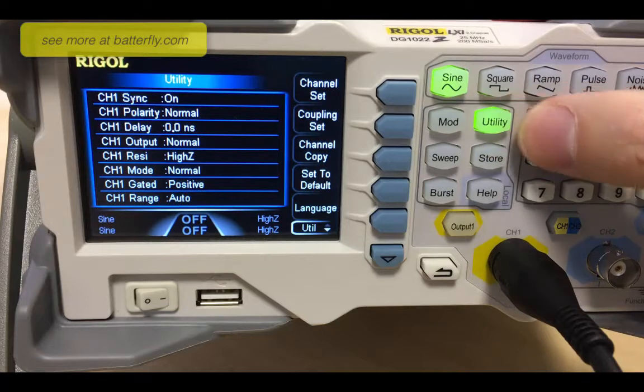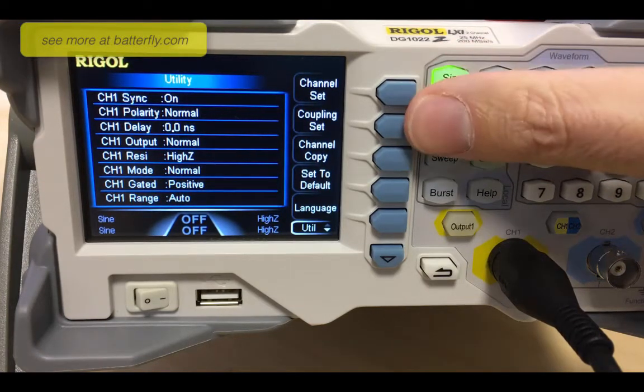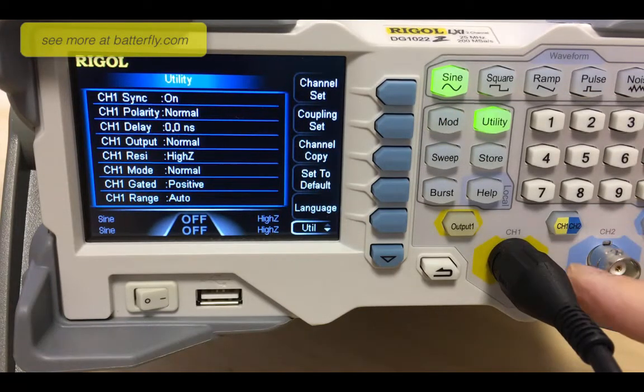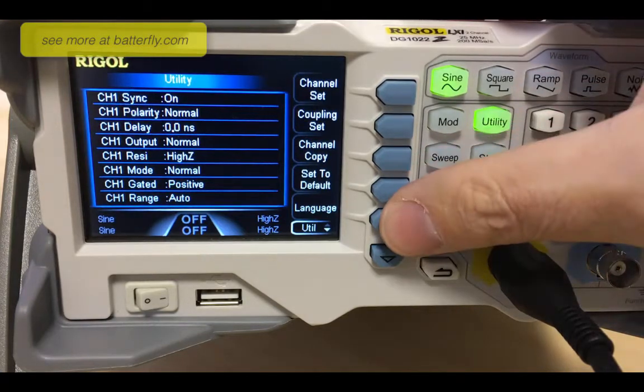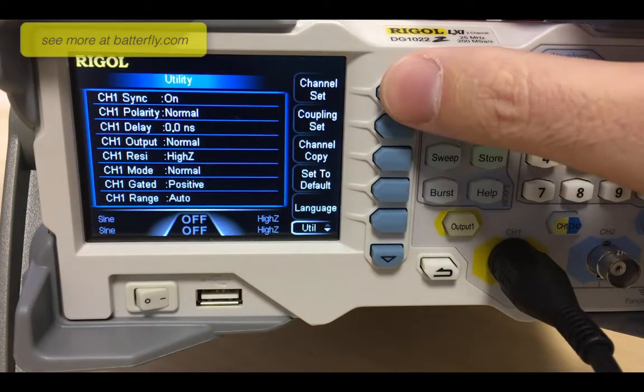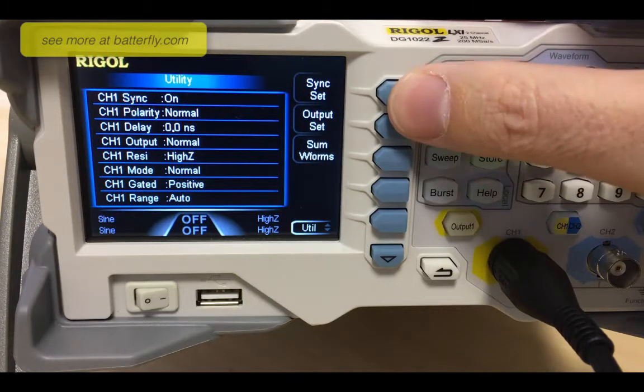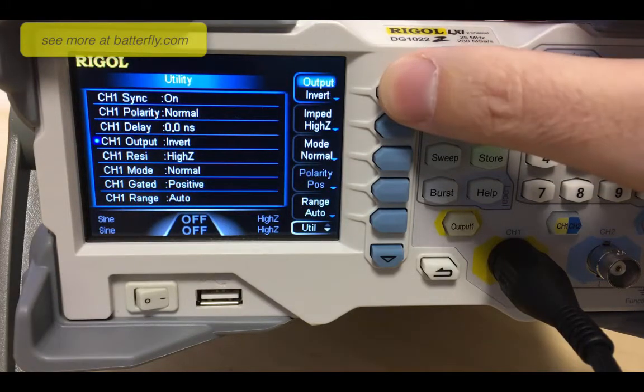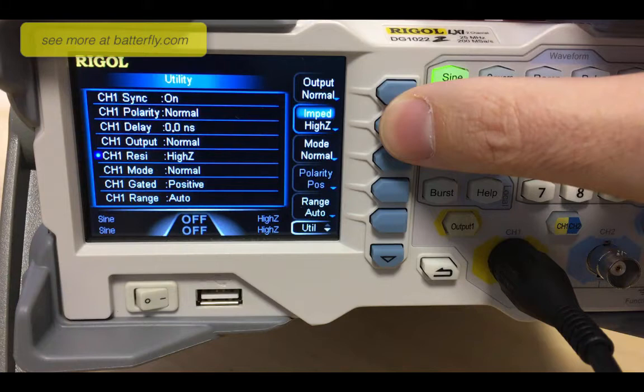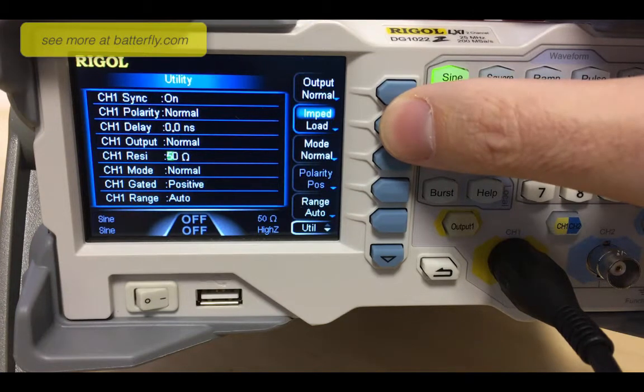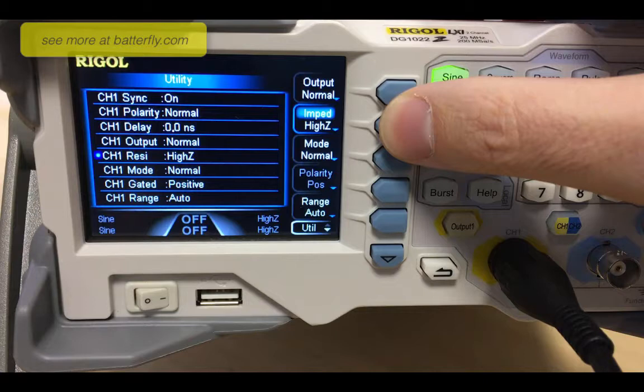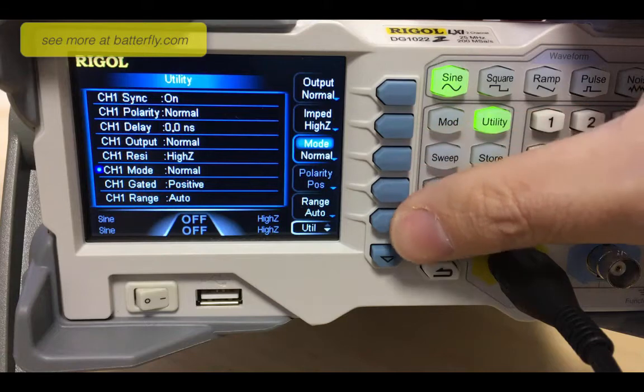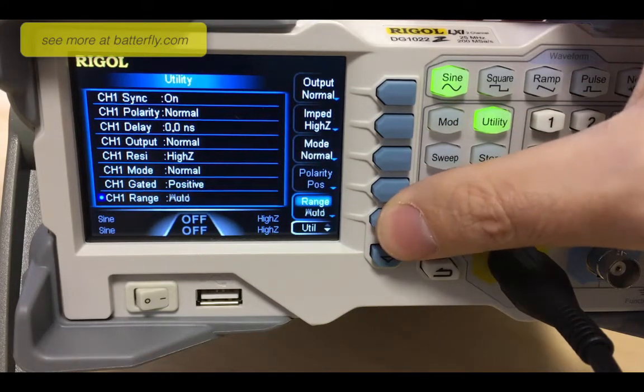We can go to the utility, where you can have the channel setup, coupling setup, channel copy - which means you can copy channel 1 to channel 2, and they are two equal units - set to default, and languages. In the output setup you can select normal or invert, move the impedance from high impedance to 50 ohm load, set the mode from normal to gated, and range from auto to hold.